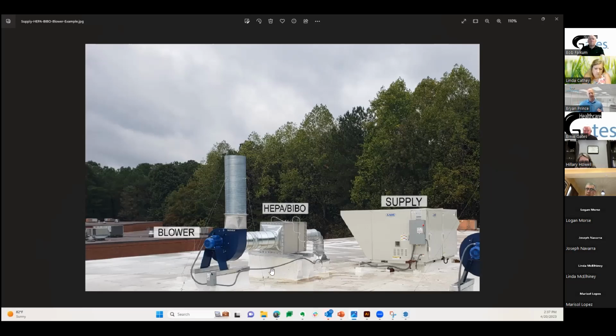However, in my example, using a low wall exhaust grille to balance the space one time instead of the powder hoods being connected, I would absolutely recommend adding HEPA filtration prior to exhaust. There's an EPA guidance document, which may have passed by now, that specifically calls out testosterone going into the water systems. Is it possible that a negligible amount of testosterone particulate could eventually find its way into the water system? Maybe, maybe not. It's up for debate. But one thing I tell pharmacies and contractors is you never want to get into an issue with a local building inspector or local EPA about the possibility of ejecting hormones out into the environment. The answer is no, you do not want to have that conversation.